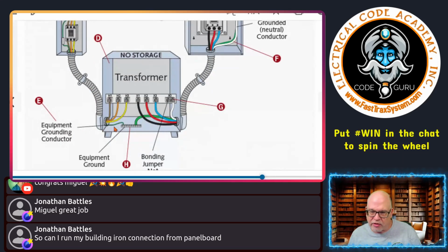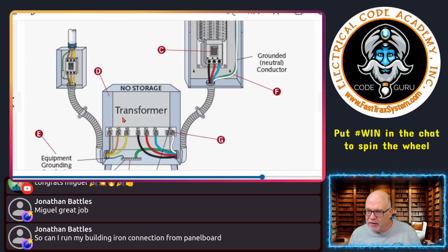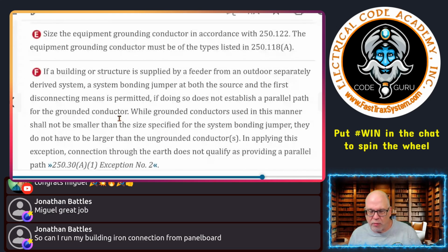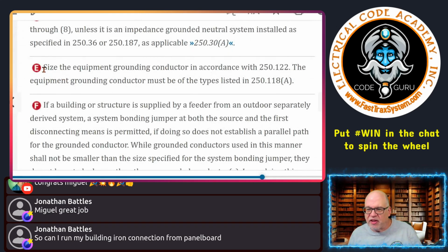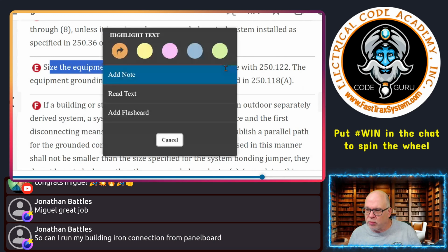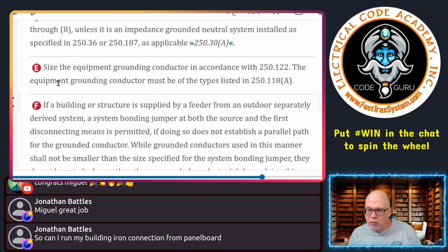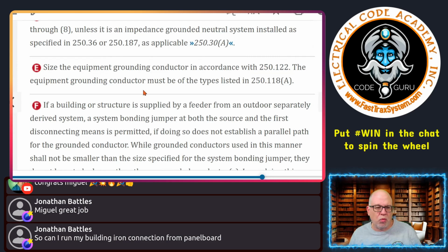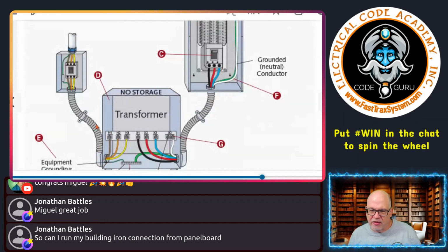So this is the equipment grounding conductor that's coming with the primary conductors, right? All right, so E, again, we're talking grounding and bonding now. It says, size the equipment grounding conductor in accordance with 250.122. The equipment grounding conductor must be of the type listed in 250.118(A). And if you go look at 250.118(A), that is the wire type in this scenario. And why is that? Because this is too large. This would not qualify as an equipment grounding conductor. So we're going to have a wire type in there.